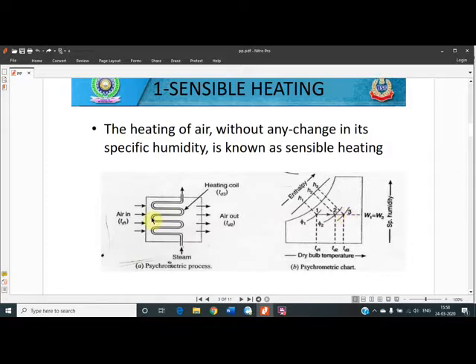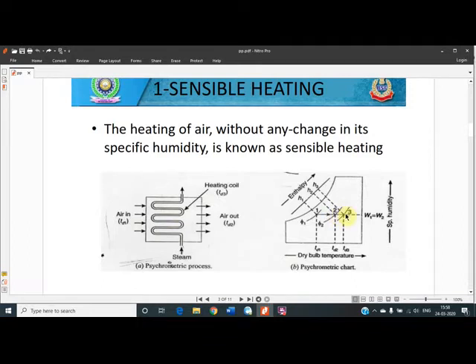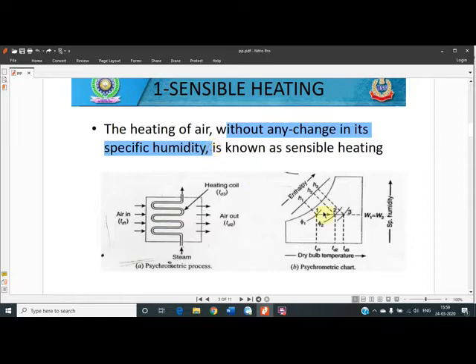This can be explained by an example: if you are using a heat pump device in winter season, the air outside is at 10 degrees centigrade and you want comfort air at 22 or 23 degrees centigrade, then the heating coil should be at a higher temperature, around 30 or 40 degrees. The first temperature is of the incoming air, second is of the air coming out, and third is of the heating coil. This process is called sensible heating because there is no change in specific humidity, that's why it is shown by a horizontal line.